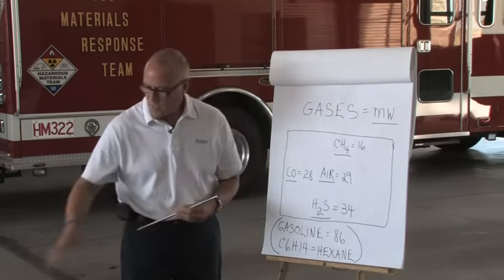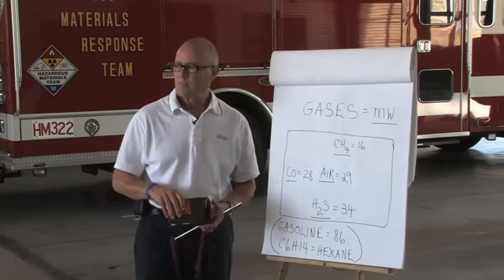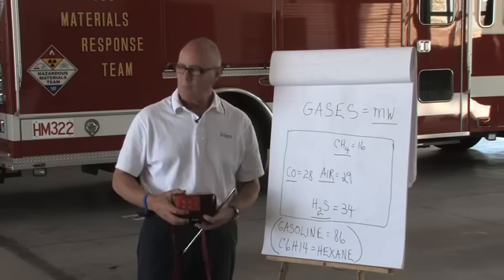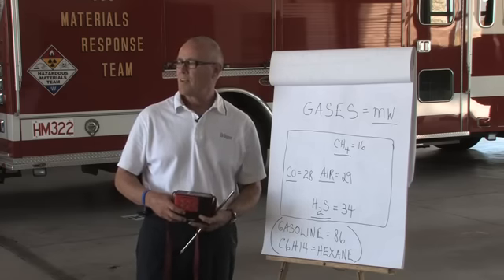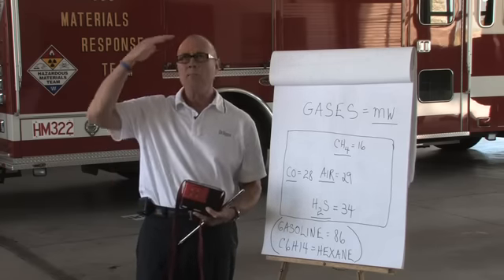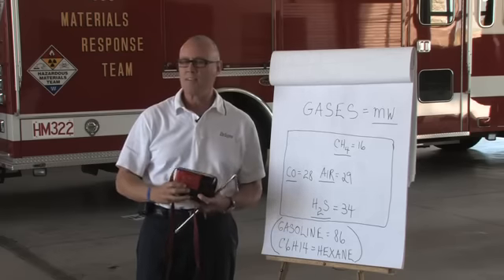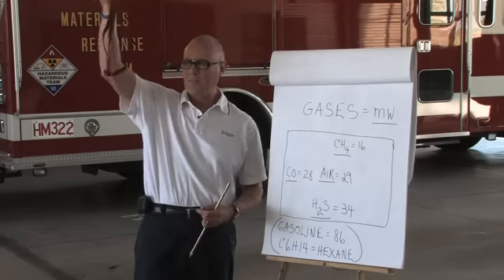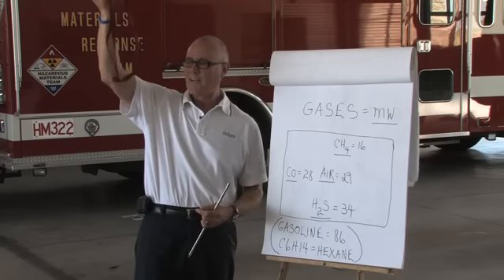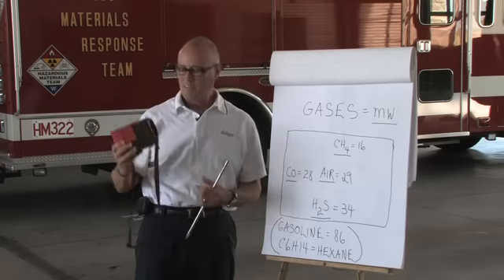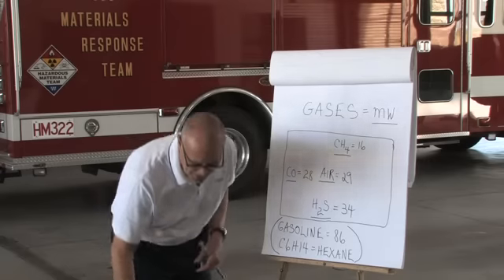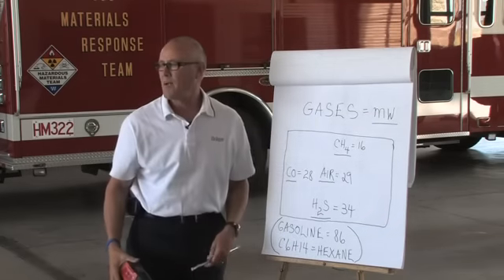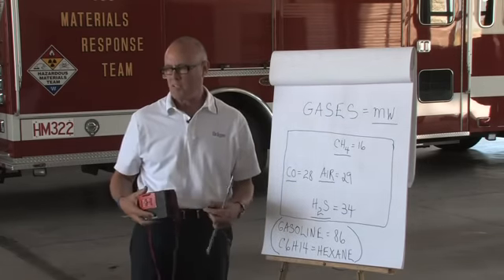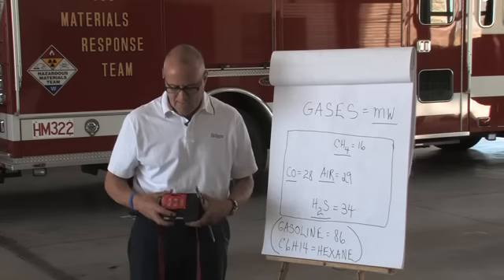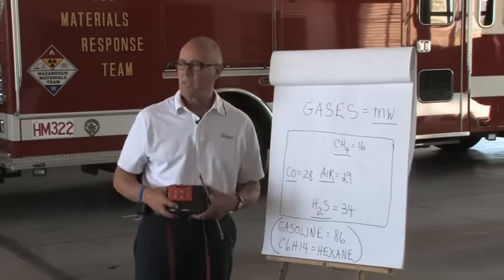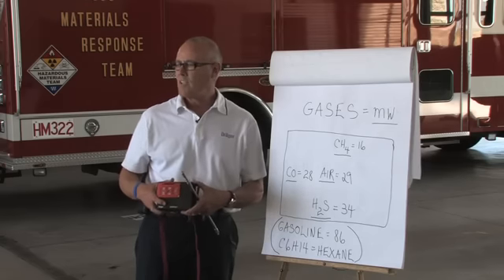So if I'm holding the instrument here, but I've got a methane gas issue that in my head might be 2 feet under the ceiling, I may want to take the meter up here to do this, and then I can detect my natural gas. In some cases, I may have to bring it down to my feet to pick up hydrogen sulfide. These are just simulations. So the gas detector can only pick up the gas from where you have it sitting.